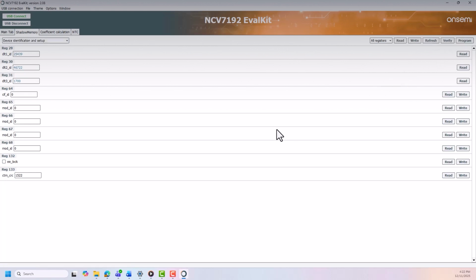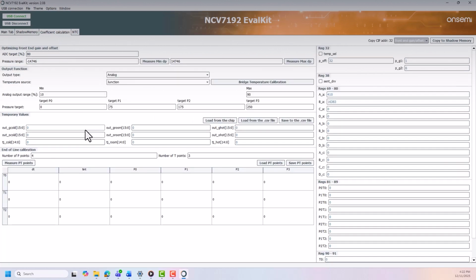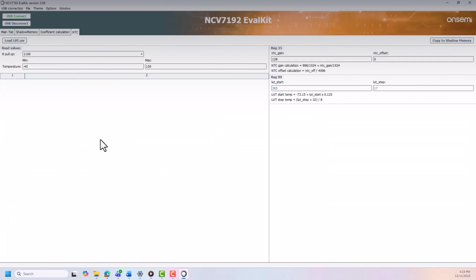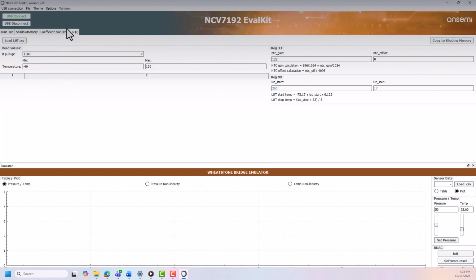Let's move to next tab, Coefficient Calculation. This tab serves for semi-automatic calculation of the device calibration coefficients and is more complex. Last tab is NTC tab, which is intended for setting NTC temperature measurement coefficients. Last important thing is the Wheatstone Bridge emulator window. You can open it by clicking on Window and select Emulator. You can even drag and drop this window where it has the most comfortable position for you.